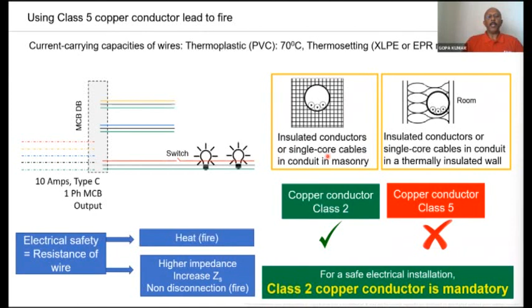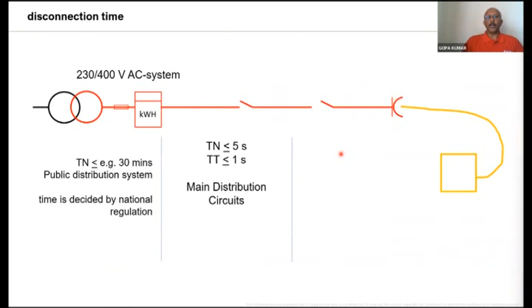All the calculations in the standard consider copper conductor of class 2, whereas in India we always use copper conductor of class 5. Class 5 copper has 8% higher resistance. 8% higher resistance means 8% higher heat in a single phase circuit, and 16% higher heat inside a conduit. The chance of getting fire from these wires is much higher. So one of my requests which I always make is, please don't use copper wires with class 5 copper conductor. You must use copper wires with class 2 conductor for any wiring inside a building, be it residential, industrial, or commercial.